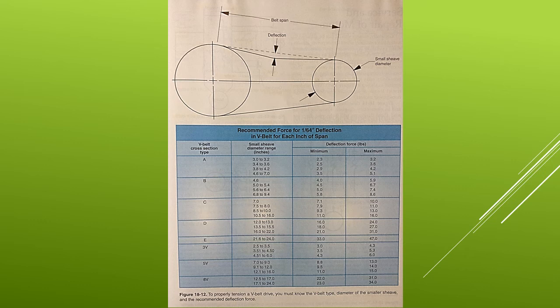Maintenance of the chain drive includes lubrication of the chain, adjustment of the chain tension, and inspection of the chain link for wear. The most common connection between a motor and a load is a belt and pulleys. Using a V-belt is the easiest and most common way of connecting a motor to a load.